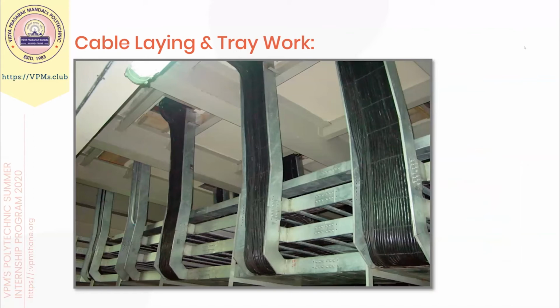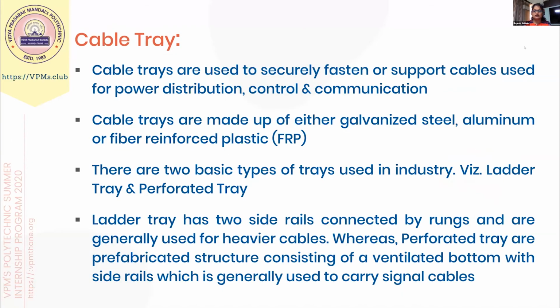Yeah, it's a ladder type tray. So we'll quickly see what a cable tray is. Cable trays are used to securely fasten or support the cables used for any purpose, like power distribution, controlling, or communication. And the cables are laid on the cable trays. Cable trays are made of either GI, that's galvanized steel, aluminum, or FRP, that is fiber reinforced plastic. There are two basic types of trays used in the industry: one is the ladder tray and the other is the perforated tray.